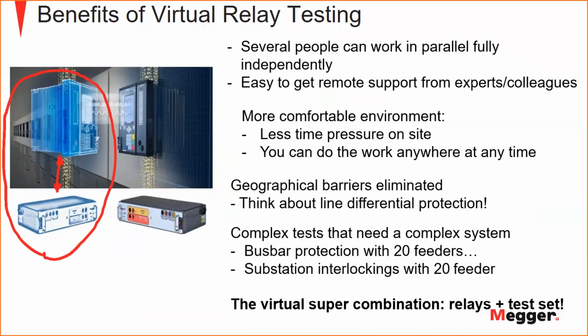So we can also invent more. We can create a test set that doesn't exist in reality, that gives you many currents, and test the complete busbar protection with 20 feeders in the virtual world. This test nobody would perform in the physical world, but it could be nice if you trust it. You trust it for 1, 2, or 3 bays. You can trust it also for 20 bays. So this was something we call a virtual super test set. A test set that doesn't exist in reality, but actually is performing the signals, voltage, and currents.